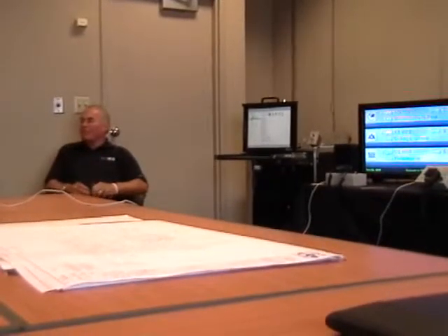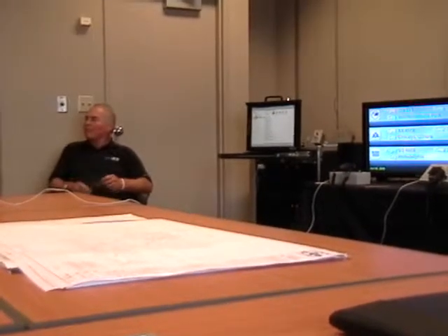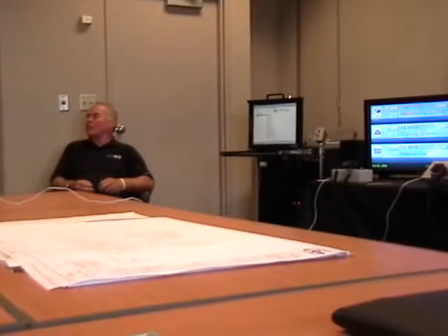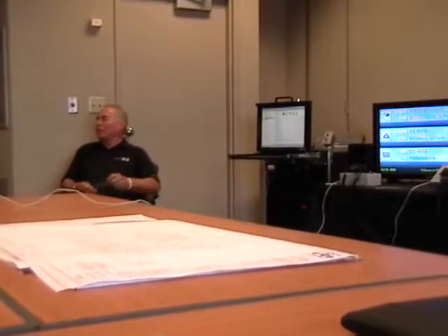And it was about 90 seconds it takes, something like that, for it to switch over. How long it takes to switch over is dependent on the number of ACSs. If you have 8 ACSs, it's probably going to take 2.5 minutes to get all that sorted out because of the number of ACSs it has. It's the time it takes to define which one went down, and all the information gets around.